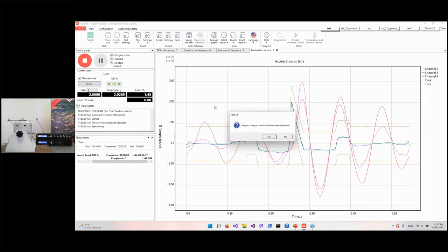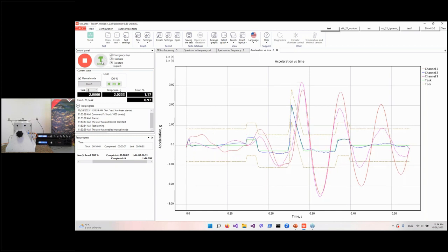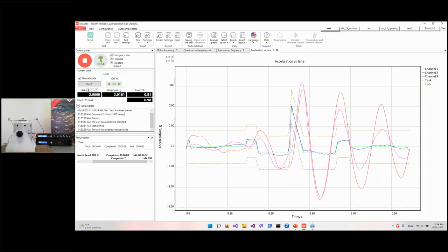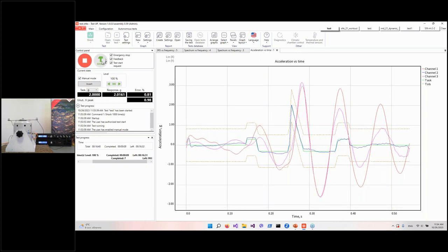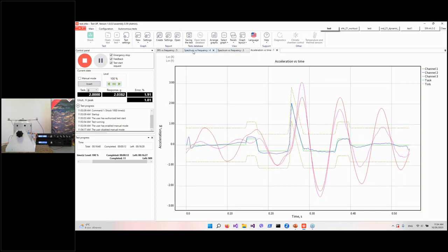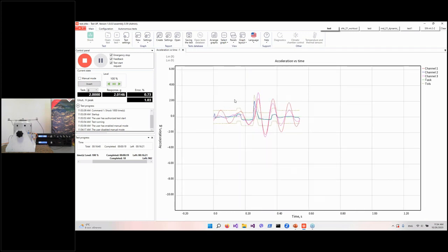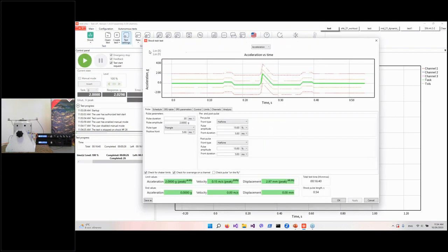During the test run, I enable manual mode and press the button — our system performs a single shock on command. After that I disable manual mode and the system continues to perform the scheduled shocks automatically. This is a very useful feature when you need to analyze every individual shock collected during the test.